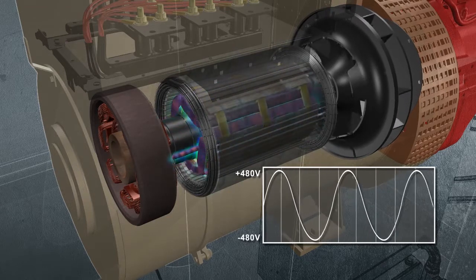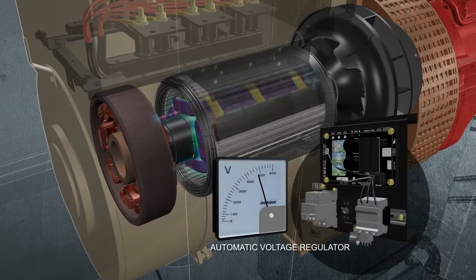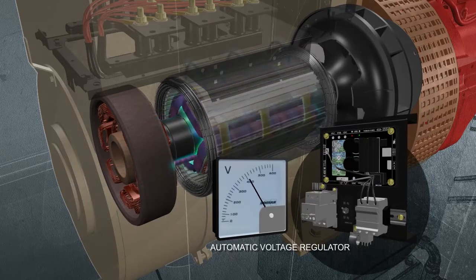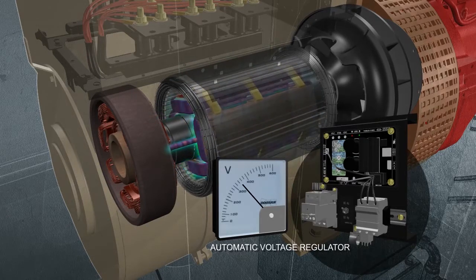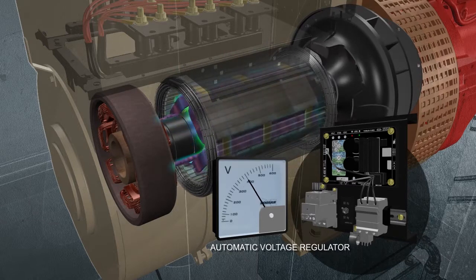To do so, an automatic voltage regulator, or AVR, adjusts the magnetic fields as needed. During heavy power demands, voltage decreases, causing the AVR to increase the magnetic field. Conversely, when power demands are low, the AVR tempers the field.